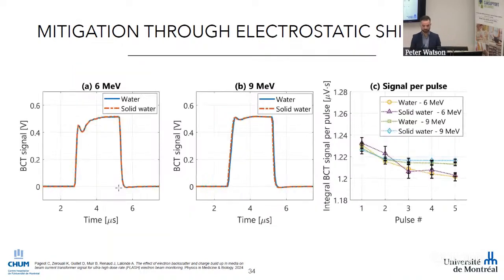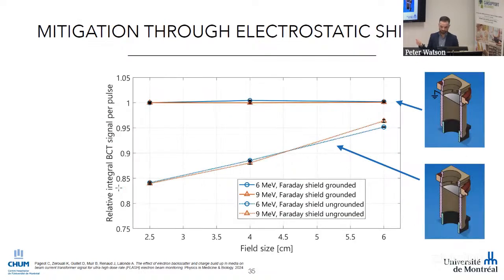It also solved the water to solid water difference. Now we have a perfect agreement for the signal we measure when we irradiate water versus solid water, as one should expect. And it also resolved the field size dependence that I showed earlier. So this really clearly indicated that what we were seeing was an artifact induced by the charge buildup occurring in plastic. Not only the solid water, the collimators were also creating this artifact. And we could prevent the electric field lines from reaching the BCT to solve the issue.